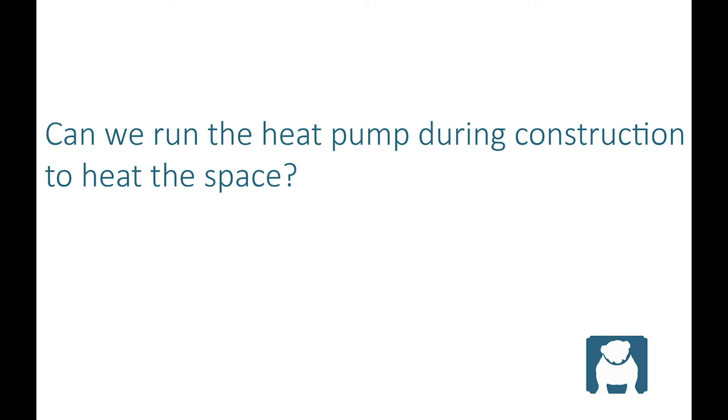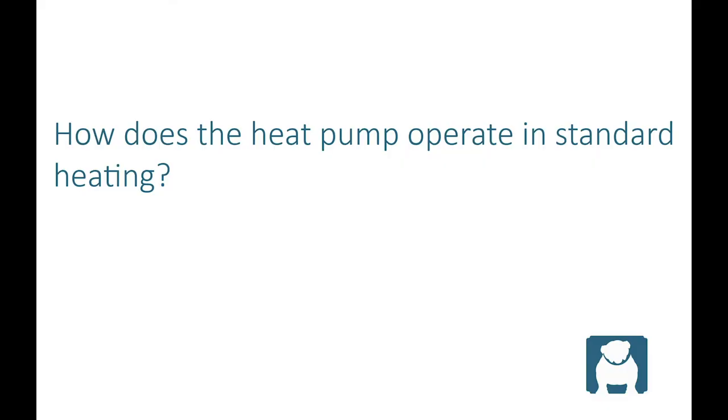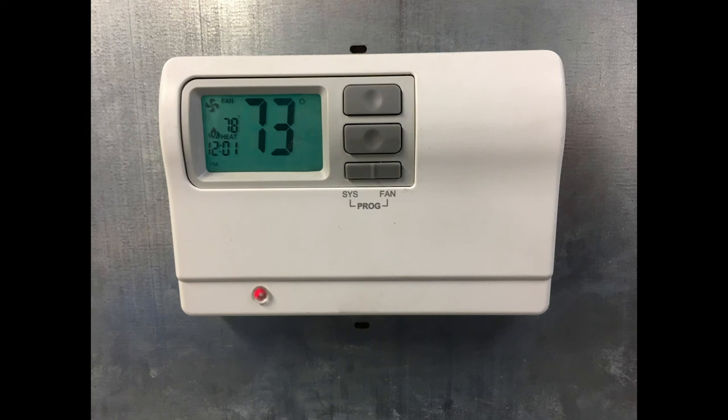Heat pumps should not be run during the construction phase of the project. Chemical vapors in the air can cause formicary corrosion of the evaporator coil. Drywall dust can clog up the evaporator coil and cause low performance of the fan motors and wicking of the fan motor bearing oil.